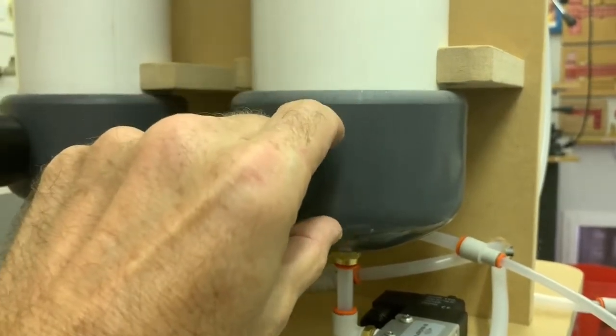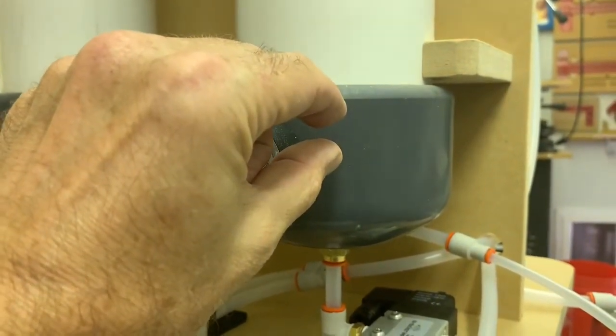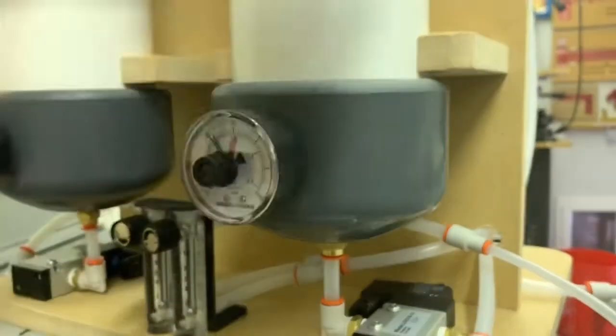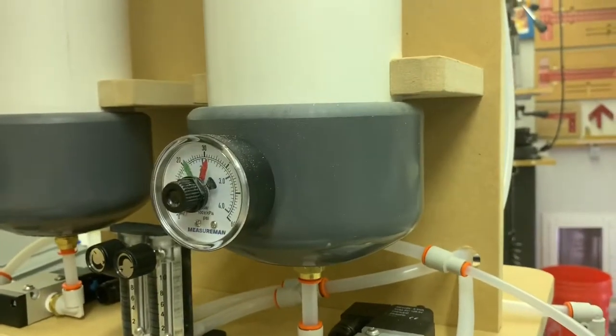So there's a one-eighth inch gap between the bottom of the filter plate where the zeolite starts. So very little wasted air there.